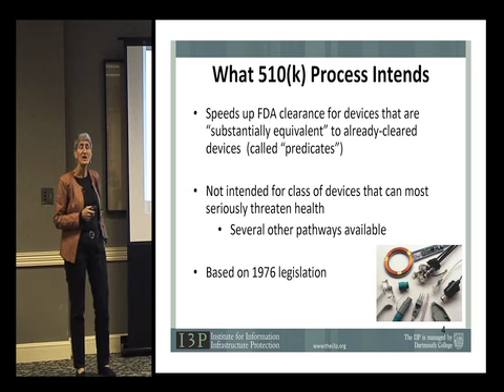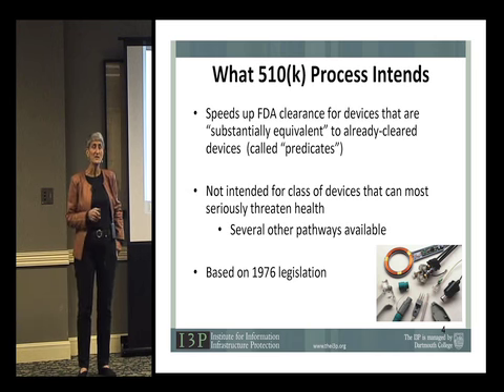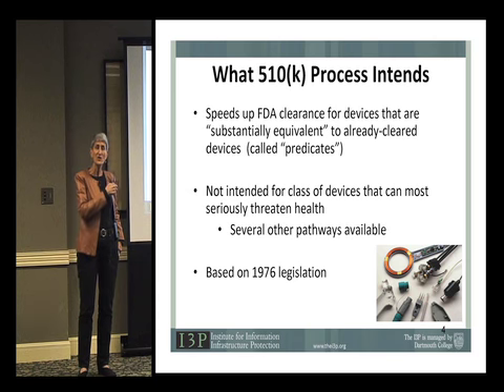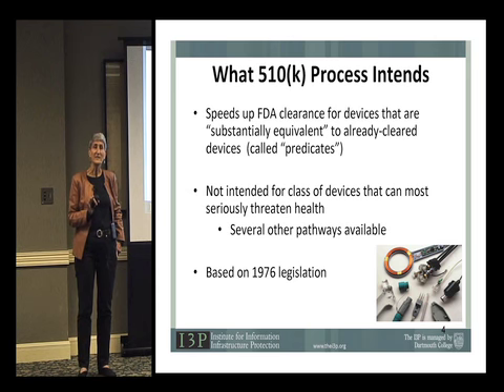Now, what does the 510K process intend? Well, normally, for a new device, it takes a long time to get approval. And the FDA uses two terms for what you and I would call approval. One is approval with the regular long-term process. The other, going through 510K, is called a clearance process. That is, the FDA doesn't approve the use of the device. It clears it for use based on evidence that, according to the 510K process, it's substantially equivalent to a device that's been approved. So that's the idea of the fast tracking that you can get through 510K. The idea is, if you're making small changes, small enough to be considered substantially equivalent to something that's gone through the longer process, then you can show the evidence of substantial equivalence, and that makes it the same, and so they fast-track the process.